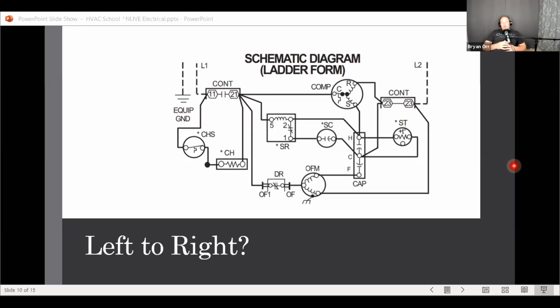And that's actually a weird one too, because it can actually be both ways. It's tricky because you can have a shorted solenoid, which is what you had. But the other thing that you got to be careful with is that solenoids do run low ohms by themselves, because it's that inductive reactance that shows up, because a solenoid is a magnet. I mean, that's really what it is. And in some cases, for example, this is a good example: if you pull a solenoid off of the reversing valve and you energize it, the thing will overamp and it will overheat, and it can actually fail that way.